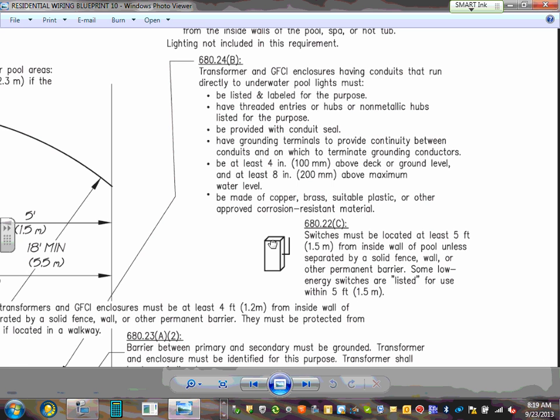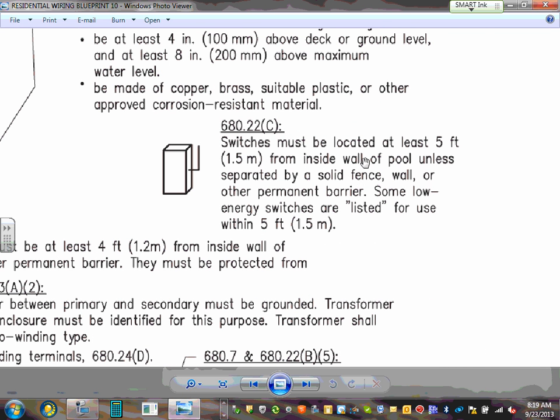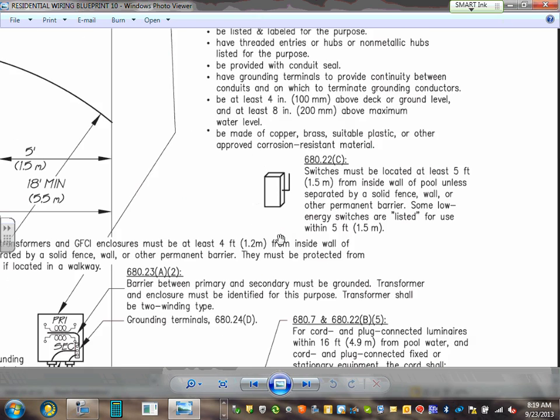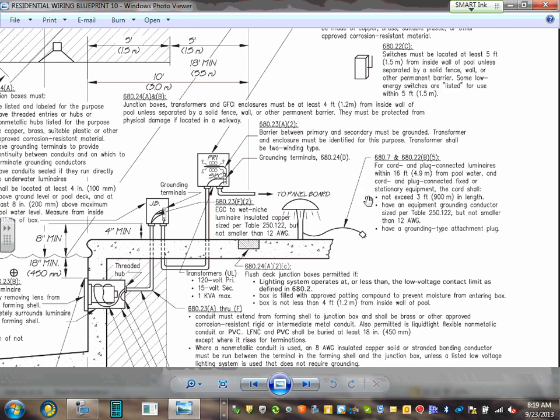Let me go. Okay, switches. Switches must be located at least 5 feet from the inside of the swimming pool, unless separated by a solid fence or wall. Some low voltage switches are listed for within the 5 feet, but typically 5 feet is the magic number.